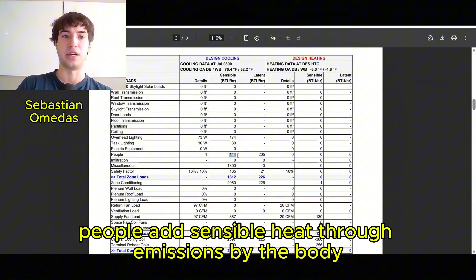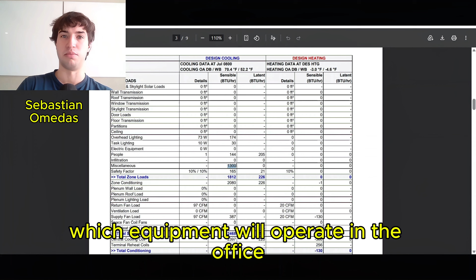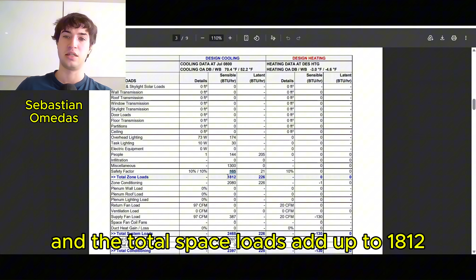There's one person in the office. People add sensible heat through emissions by the body and latent heat through sweat. We group the equipment loads in the miscellaneous section, and we've chosen which equipment will operate in the office. The factor of safety helps account for the negligible heat that fenestration adds, and the total space loads add up to 1812 BTU per hour.